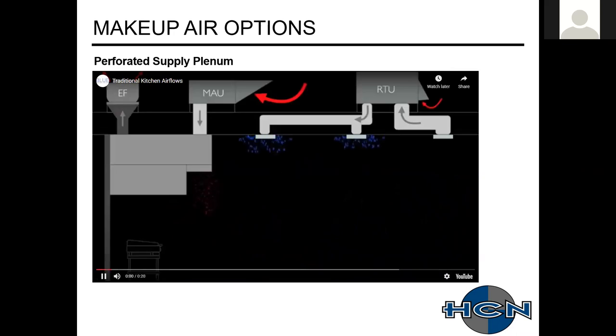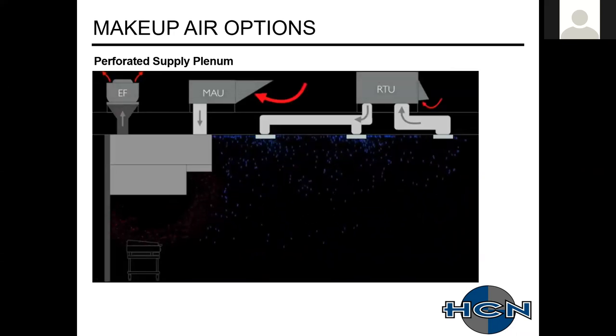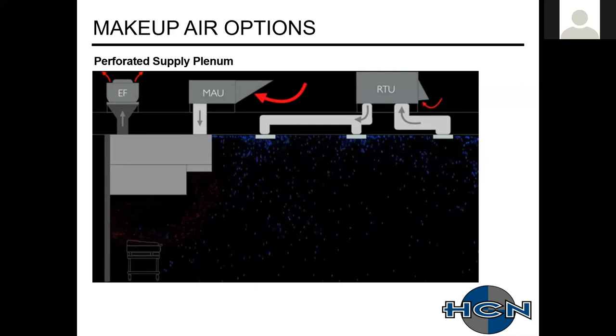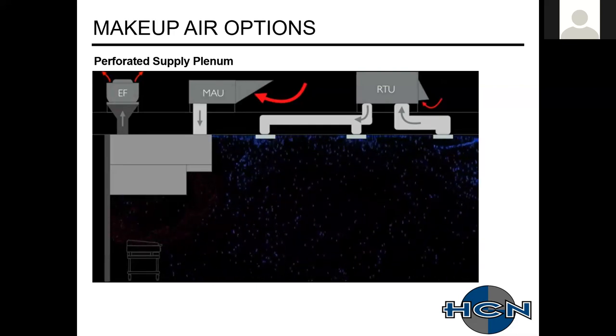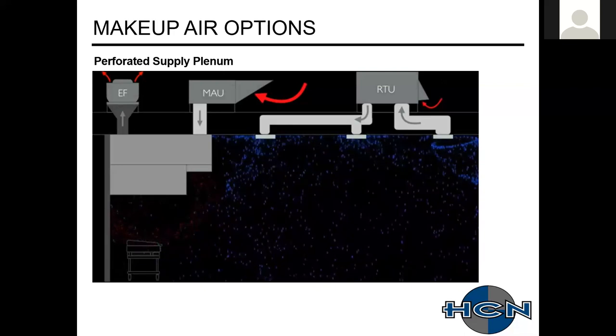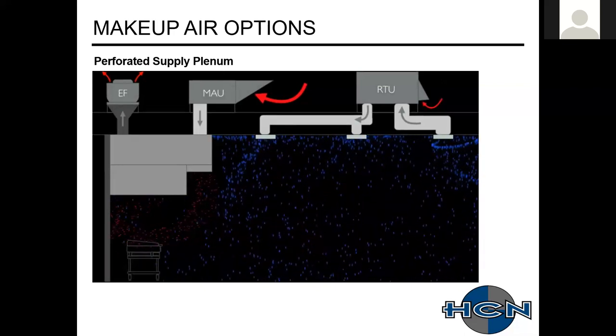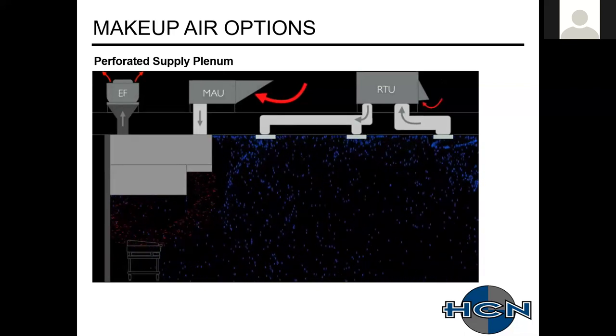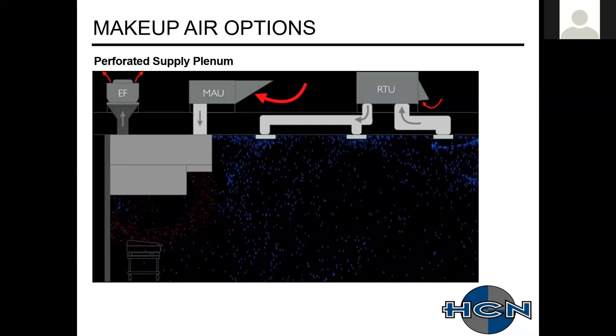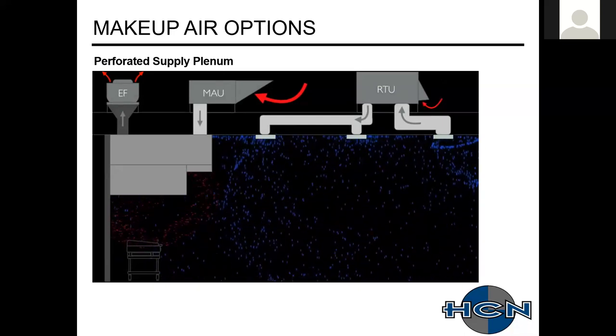This diagram I got from a colleague that I used to work with. He's over at Blue Energy Engineering down in Kentucky. So Zach Scott did all this. This is the typical system for a makeup air plenum. If everything's working properly, you have the proper velocities and proper temperatures, and that makeup air is not diffusing into the space. It's doing what it's supposed to do, going right back in the hood. It's not affecting your rooftop unit or the temperatures in the space.